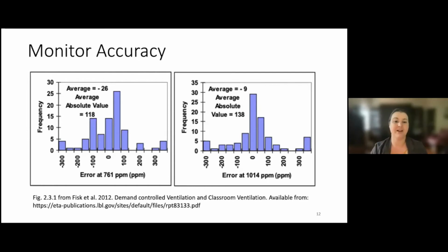They were also, theoretically, calibrated at installation, and they were supposed to be calibrated once per year. You can see from these two graphs, which are from this paper down here, that at this upper measurement point around 1,000 ppm, only about 30 of the sensors were dead on. The rest varied in these two tails, being above or below the actual true value. When they went down to a lower measurement point around 760 ppm, this flattened out a bit more, so more of the sensors became inaccurate. That's a really big concern.